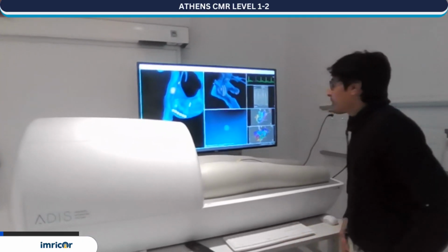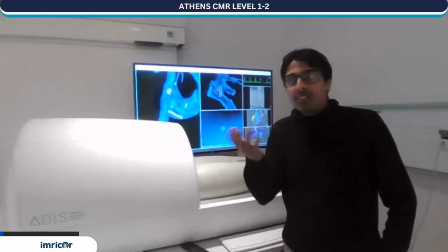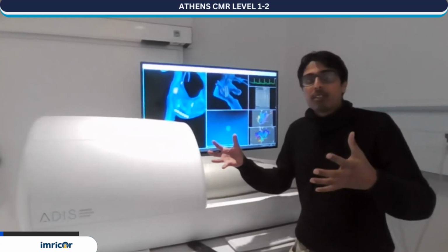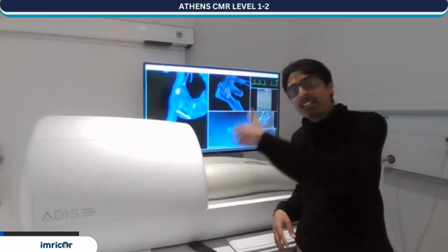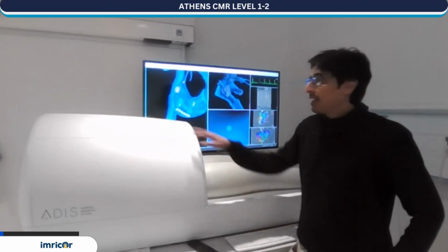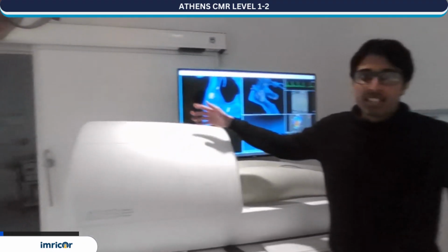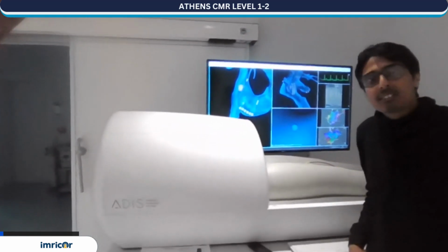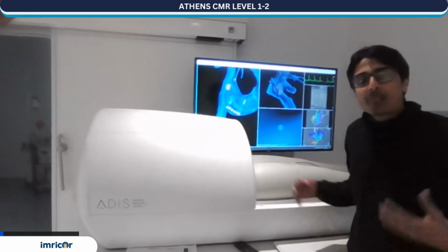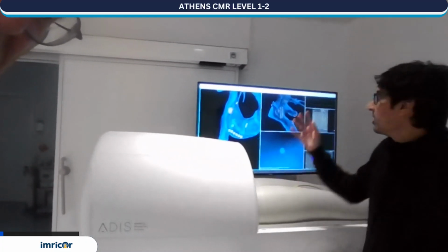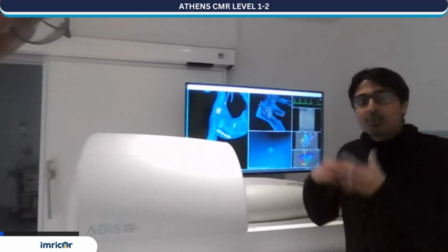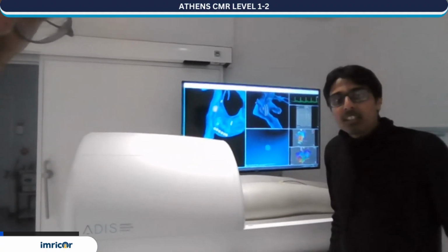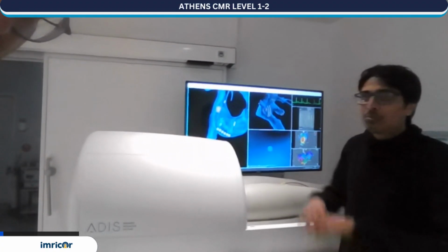And the 3D model of the heart is coming from MRI or CT. You use the MRI or the CT to extract the 3D model, and then we loaded it into the system. And in the system here, you see it's a chamber, basically an empty chamber, where you maneuver the physical catheter. We track this physical catheter and we move it inside the virtual heart so that it reflects a virtual scenario where you are doing maneuvering and ablation inside the chamber of the heart. Yeah, so that's more or less it.